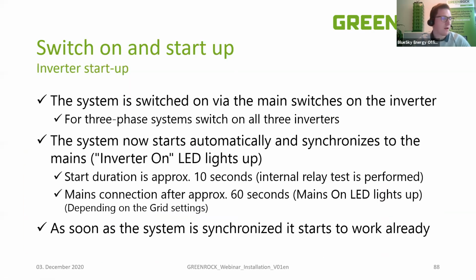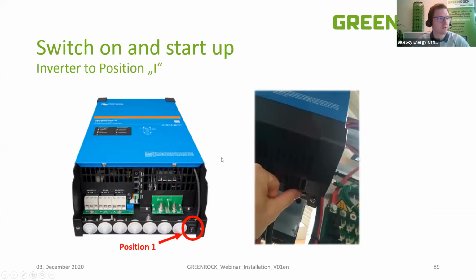We continue: once connected to the web interface, we can switch on the system. This is done via the inverter, the Victron Multiplus 2, which has a power switch on the bottom right. Push it to position 1. This is important because it's a 3-position switch: you can use 0, 1, or 2. Position 2 is only a charge command, meaning the battery is not allowed to discharge. So you need to place it on position 1, pushed inside.